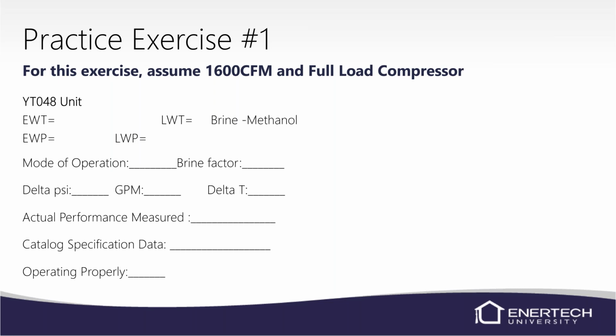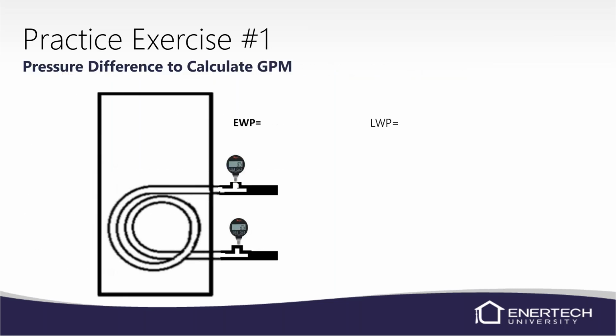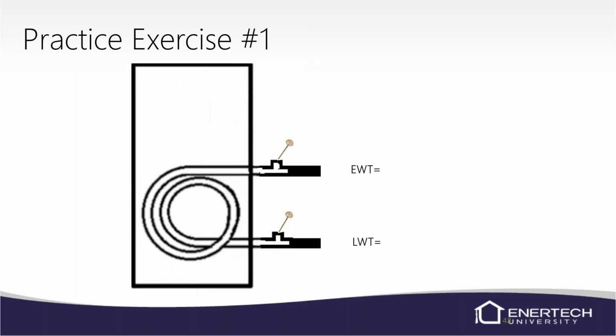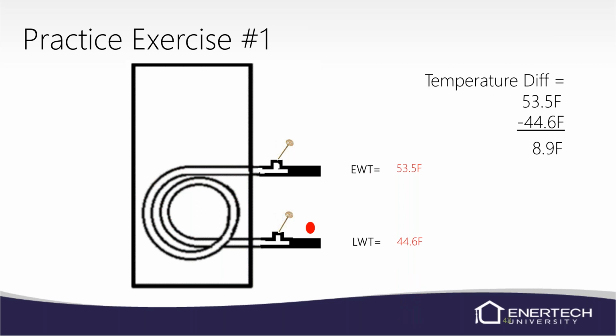So we've got a YT unit 048, so we've got a packaged unit, 4-ton. Our brine is methanol. We've got an entering water pressure of 49 and a leaving water pressure of 46. Pretty easy to do the math on that. 3-pound pressure drop, so we'll make a note of that. While you're there, go ahead and do your temperature difference at the unit. So we have 53.5 in and 44.6 out.